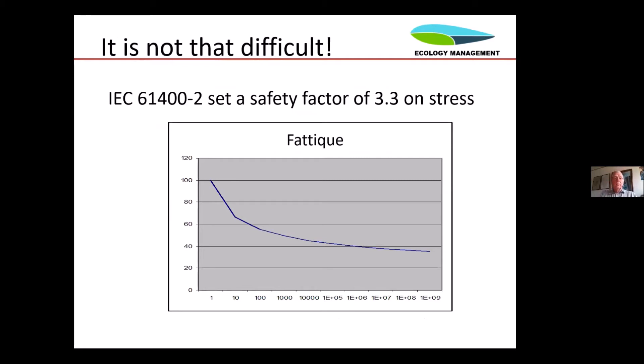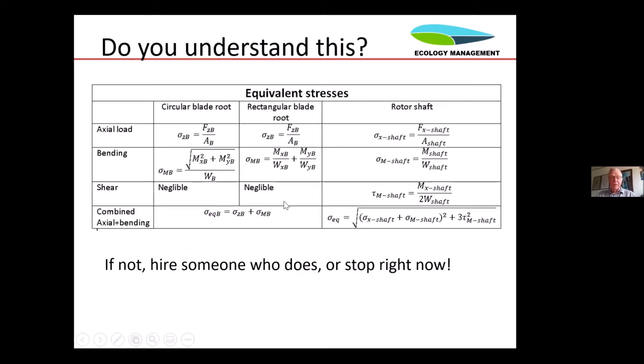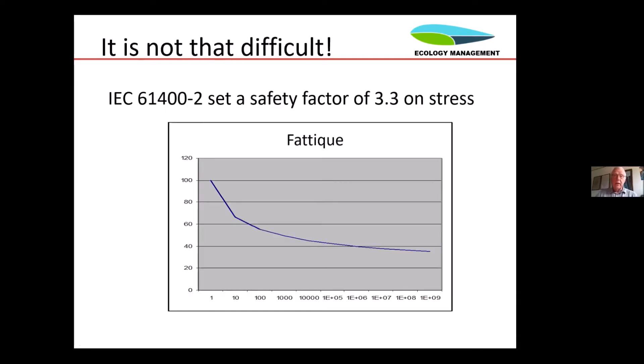Going back to the IEC standard, one of the things where the Dash 2 differs significantly on a mechanical scale from Dash 1 and Dash 3 is that you don't have to do fatigue calculations. You're welcome to do it if you want, but you don't have to, because you can use a safety factor of 3.3 on stress. And if you use that, you can see in the S-N curve that you are well out in terms of number of load cycles. So as long as you stay at a safety margin of 3.3 or higher, fatigue is not an issue.